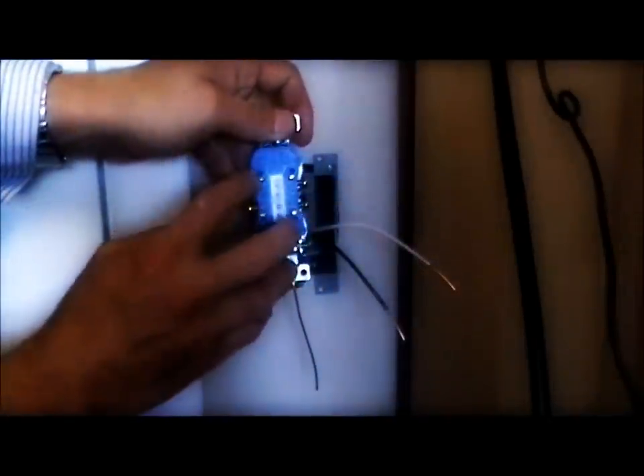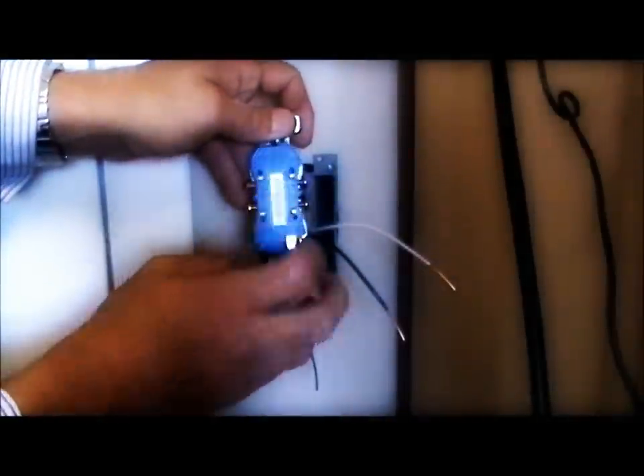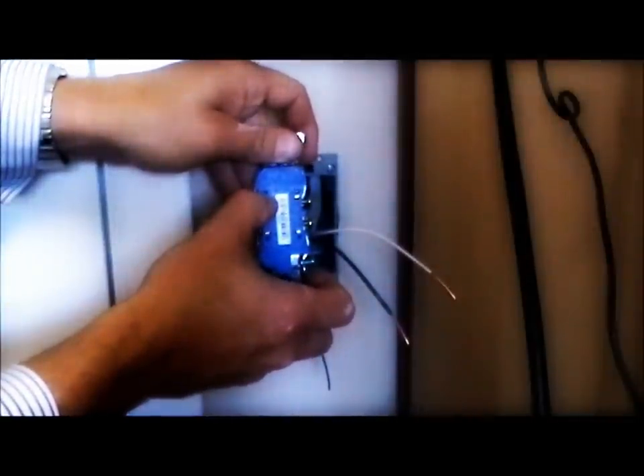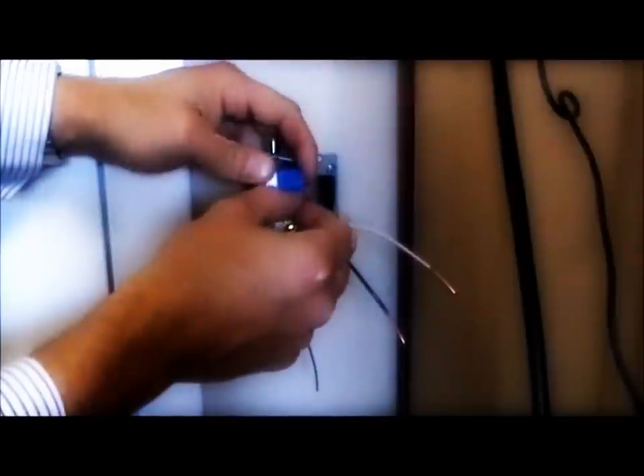Now, modern outlets have quick connects in the back. We, as a company, we do not use them. They have a tendency to get loose and they trip arc fault breakers. So what we do is we make the wires so they go around the screws, which is a much better and tighter connection.